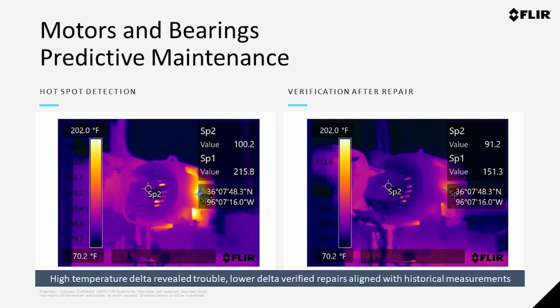Oh yeah, okay. I mean, I'm not a motor expert. I couldn't say what kind of repair was made, but they did identify that for some reason that motor's running hot. Was it something on the pump side, the machinery that it's driving? Was it a problem with the motor itself? Was it a problem with the power supply? I don't know. But once repairs were made, the thermographer was able to come back, take a similar image, and verify that, okay, now it's running at an external temperature that is more in line with the historical trend. Problem solved. At least by that variable, they're able to verify.